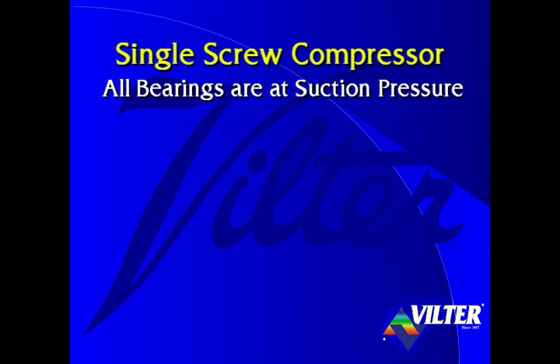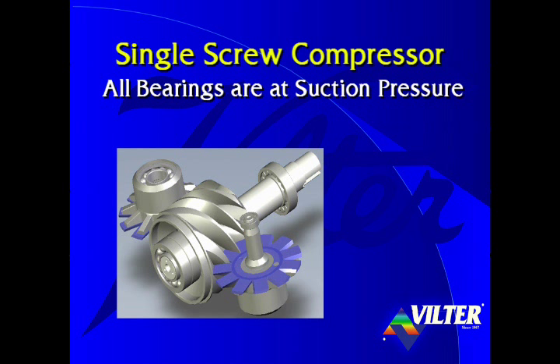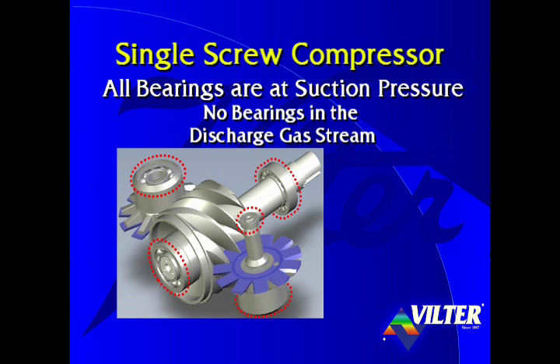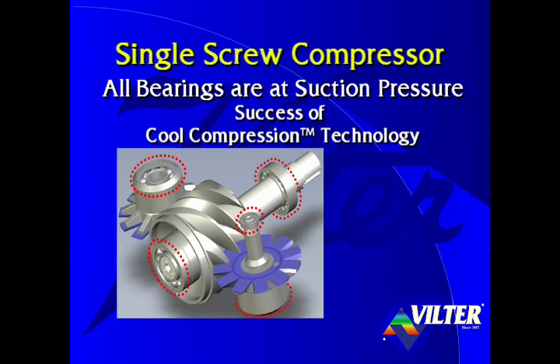All of the single screw compressor's bearings are at suction pressure. With the single screw, there is no risk of bearing degradation or failure due to liquid ammonia washing oil off the bearings in the discharge gas stream, since there are no bearings in the discharge gas stream. This feature of the single screw allows the success of Vilter's Cool Compression technology.